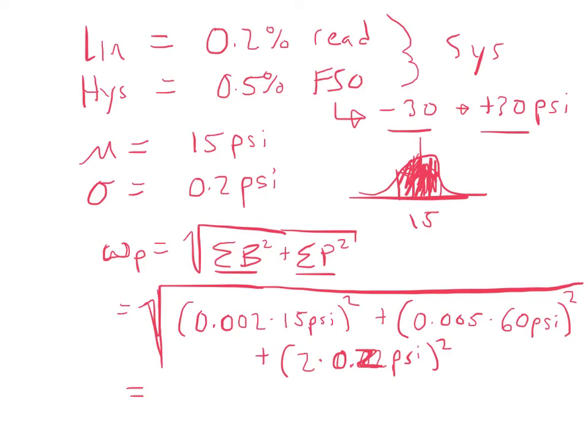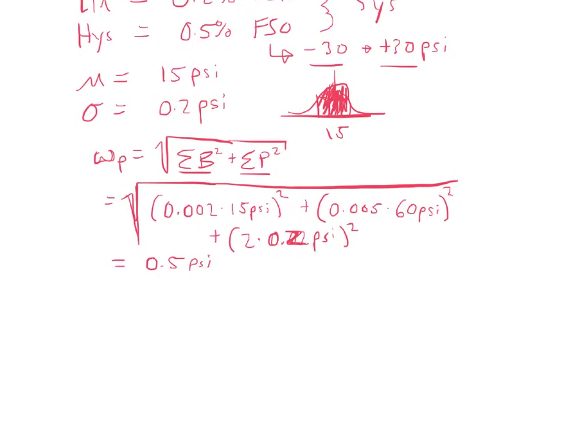Square root of sum of squares, all that together. It gives us a total error of 0.5 psi. So, now, what we can say with this is we have a 95% confidence that our pressure is the mean plus or minus that error. So, we're 95% sure that our measurement is 15 plus or minus 0.5 psi.